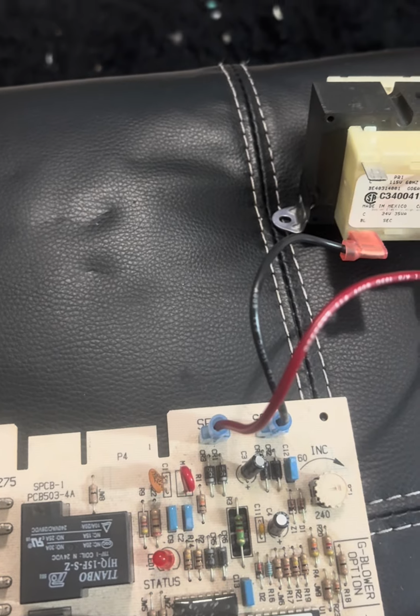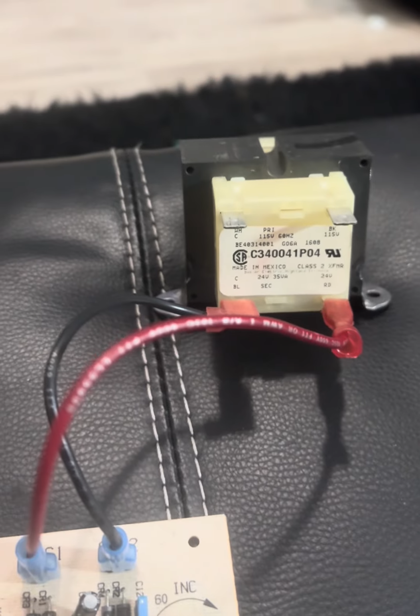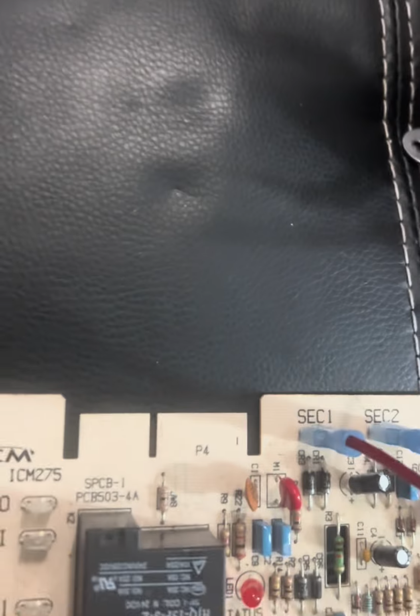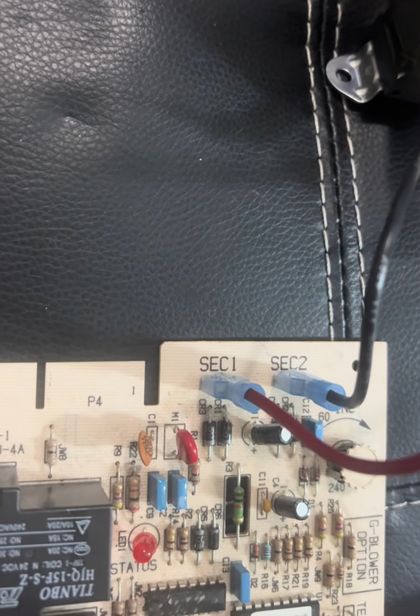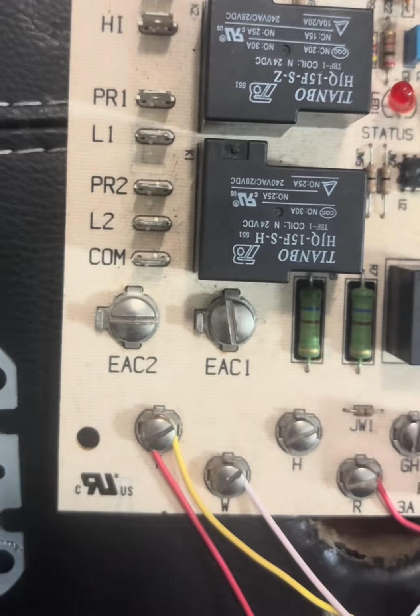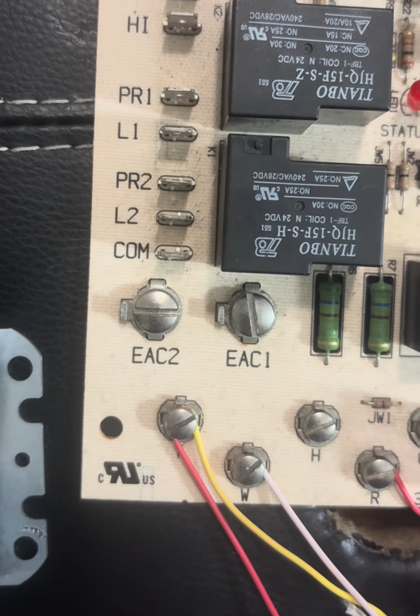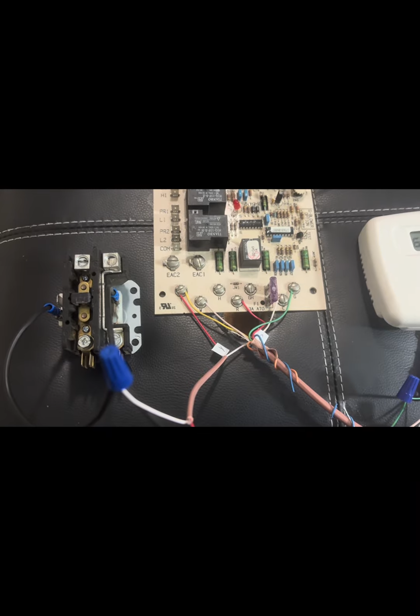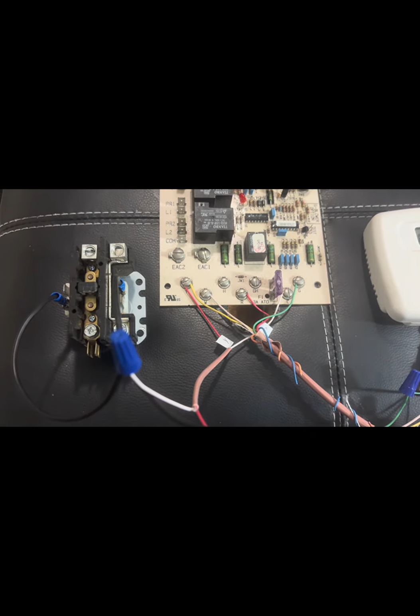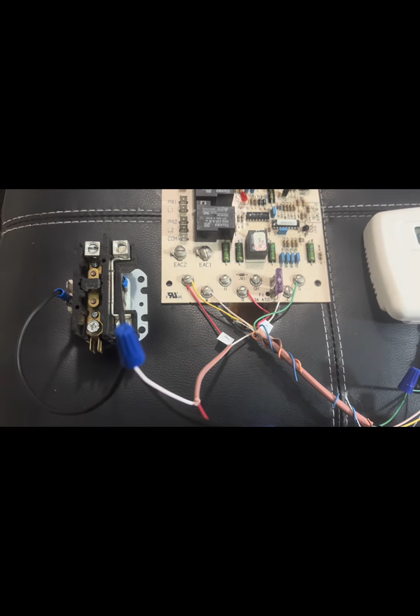For this particular wiring for this transformer, this was kind of the only best one I had to give this example. That will go right here on your secondary 1 and your secondary 2, and your primary side will go on the primary 1 and primary 2. Contactor for the outdoor unit. When the wire is energized, the coil pulls in the contacts.